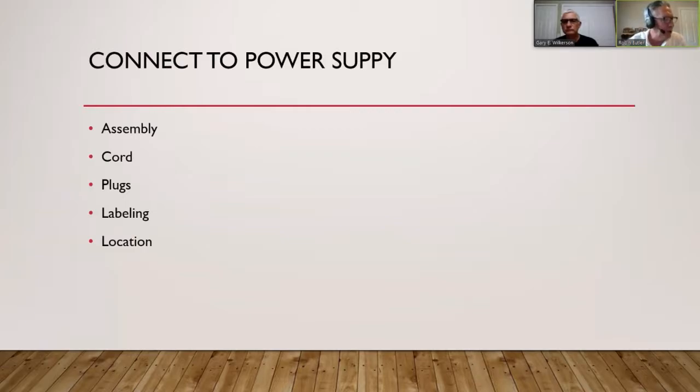Here in the book, it says that the cord exposed usable length measured to the point of entry on the vehicle exterior shall be a minimum of 25 feet, where the point of entrance is at the side of the vehicle, or a minimum of 30 feet, where the point of entrance is at the rear of the vehicle.